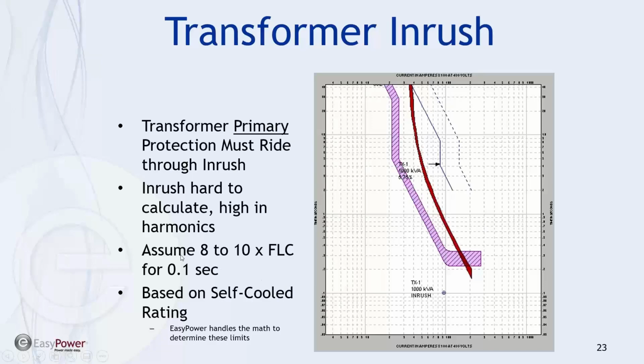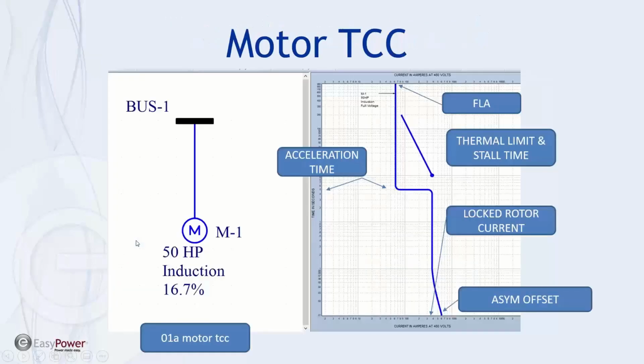All right, so then the last thing I wanted to cover was motor time current characteristic curves. And just like the transformer, all this is based upon data that we collect when we're drawing the one line, or we're collecting data for the model in EasyPower. And the TCC looks like a chair for a motor starting curve, at least an induction motor. And these all have relevance to parameters in the setup. We'll get into EasyPower and look at that.